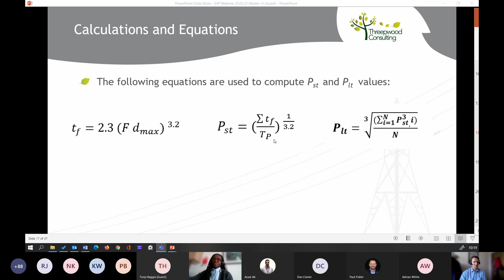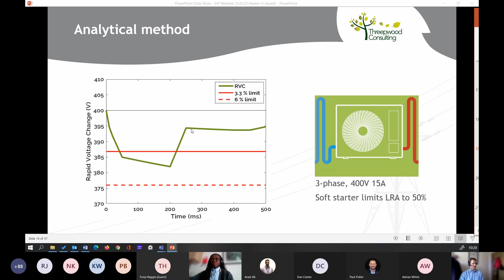Yes, this is an example we did on a much smaller heat pump, but it can also work on larger devices. We did this on a 15-amp heat pump, which had a soft starter that limited its starting current by 50%. We based it on our starting current profile, made some assumptions on the running and starting power factor, and were able to obtain the rapid voltage change. As you can see from this graph, it met all of the requirements - below 6% for the start, and the steady state is within 3.3, so it meets everything.